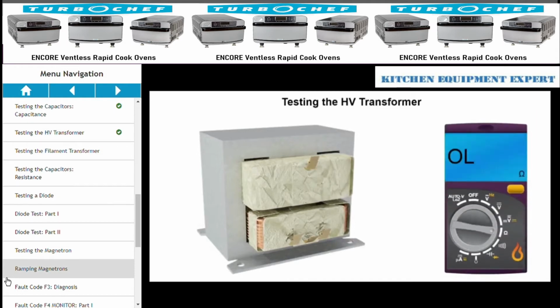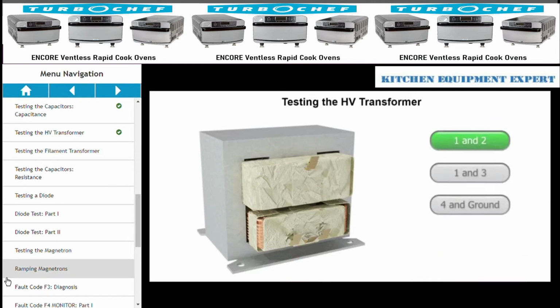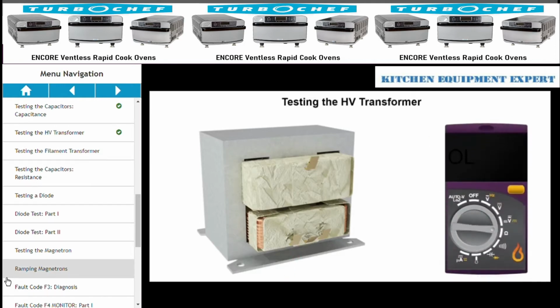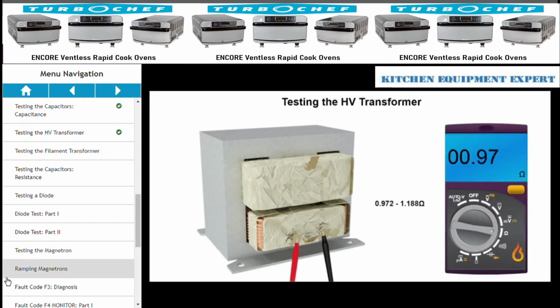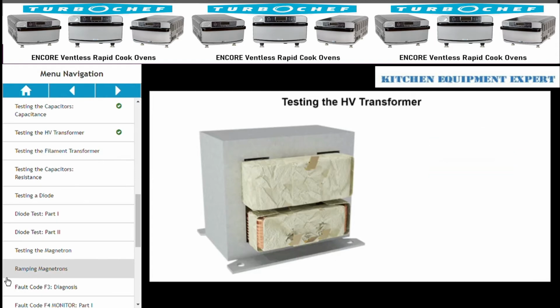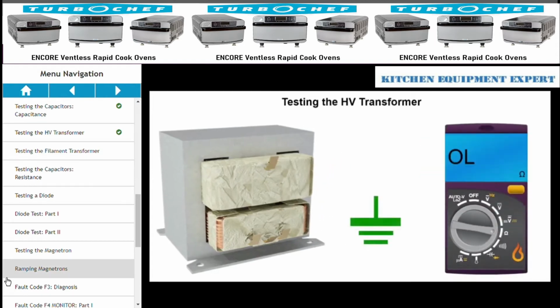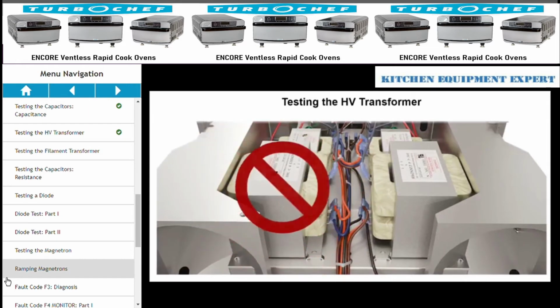With your meter set to the ohm scale, measure between terminal 1 and 2. You should see between 0.819 and 1.001 ohms. Measure between 1 and 3 and you should see between 0.972 and 1.188 ohms. With your meter set to the ohm scale, measure between a chassis ground and terminal 4. You should see between 53.6 and 65.5 ohms. Any readings outside these specs will indicate a faulty transformer.